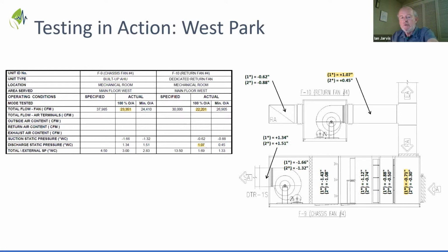And during minimum outside air, once again, we're at 27,000 return, 24,000. The return air there, in fact, is a little higher. And guess what? This is one of the hospitals that had negative pressure in the front lobby. And one of the solutions to this was to slow the return fans down further to maintain that differential between supply and return. Again, without belaboring these things, because we're going to ask you at the end how much more information you would like on this kind of interpretation stuff.